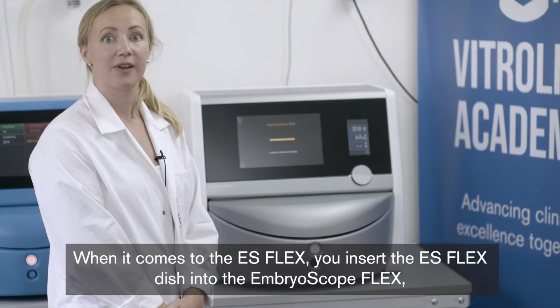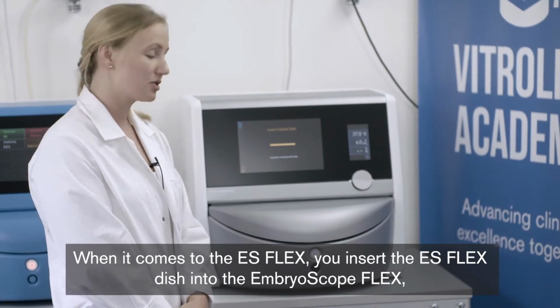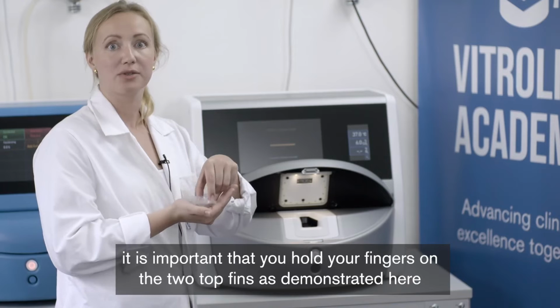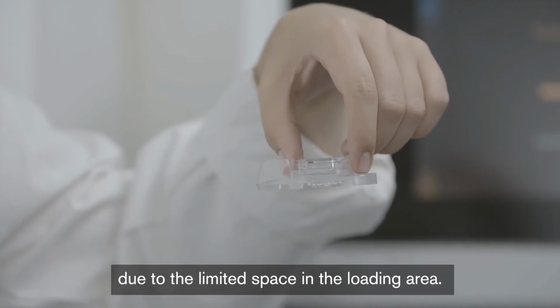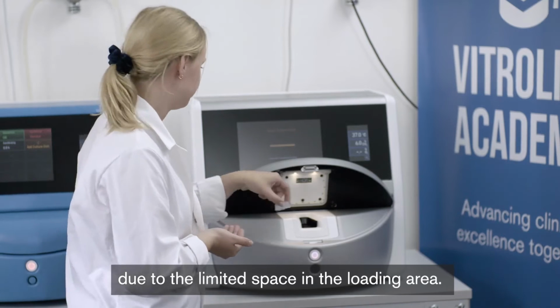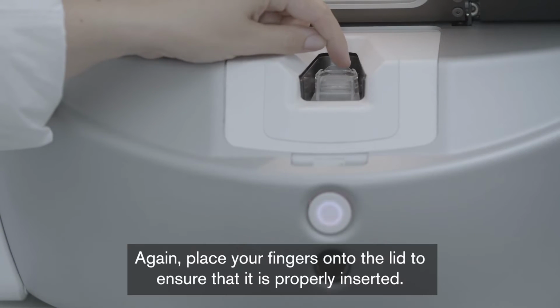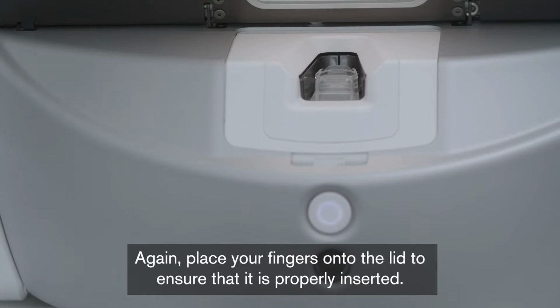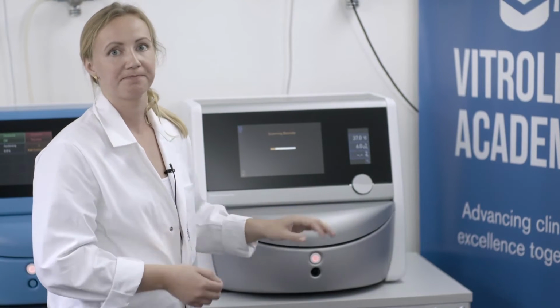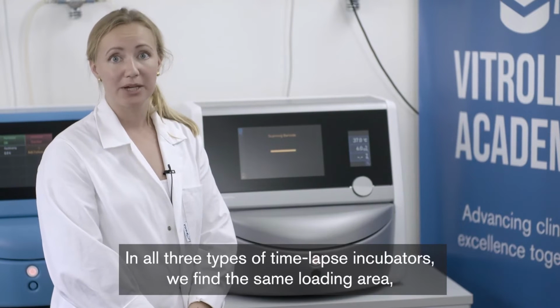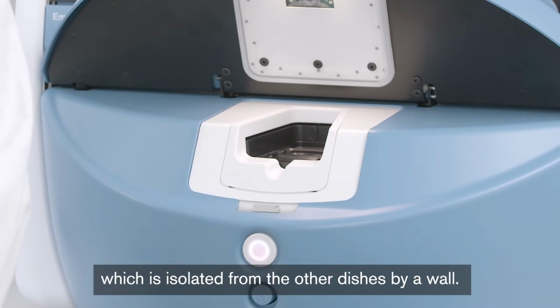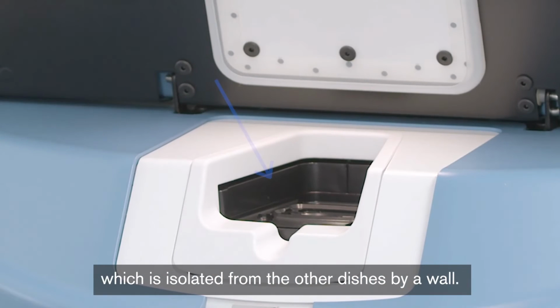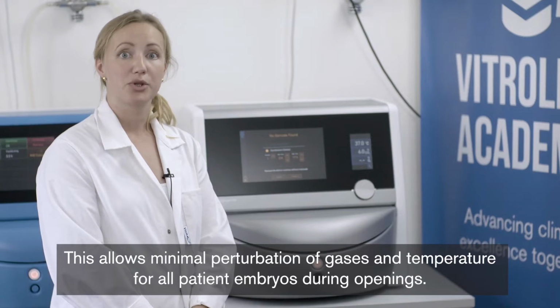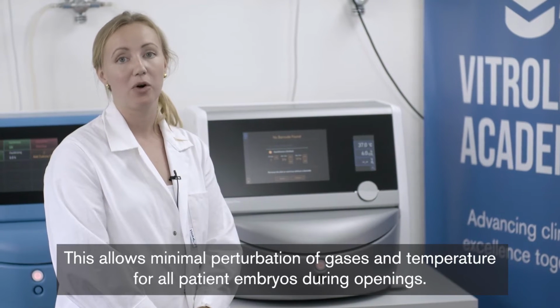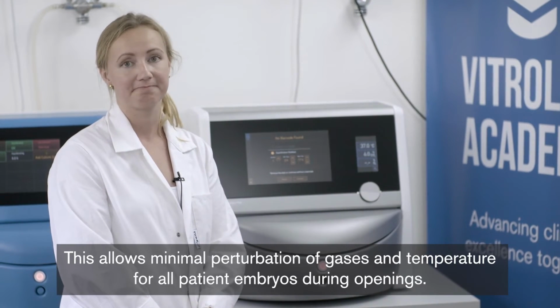When it comes to the ES Flex, you insert the ES Flex dish into the EmbryoScope Flex. It is important that you hold your fingers to the 2 top fins as demonstrated here, due to the limited space in the loading area. Again, place your fingers onto the lid to ensure that it's properly inserted. In all 3 types of time-lapse incubators, we find the same loading area, which is isolated from the other dishes by a wall. This allows minimal perturbation of gases and temperature for all patient embryos during openings.